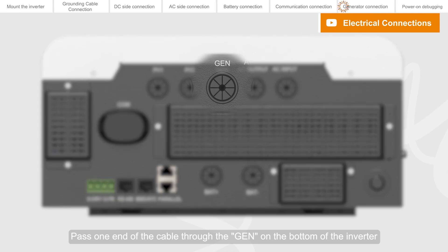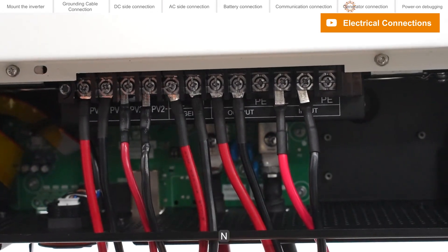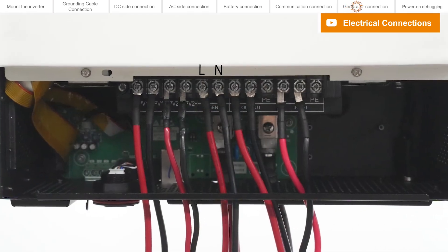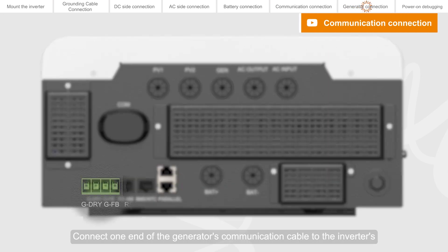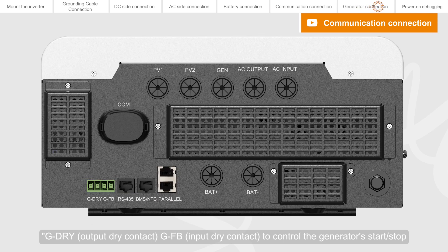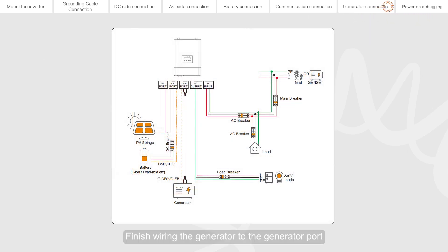Pass one end of the cable through the GEN port on the bottom of the inverter and connect to the GEN L and N corresponding ports. The other end is connected to the generator. Connect one end of the generator's communication cable to the inverter's G-DRY output dry contact and GFB input dry contact to control the generator's start or stop. The other end is connected to the corresponding port of the generator. Finish wiring the generator to the generator port.